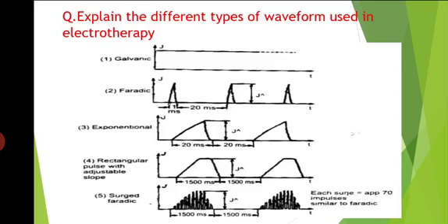Faradic current. Faradic current is a sequence of pulses with a defined shape and current intensity. The pulse duration is about 1 millisecond with a triangular waveform, and an interval duration of about 20 milliseconds. Faradic current acts upon muscle tissues and, upon the motor nerves, produces muscle contraction. There is no ion transfer and no chemical effect. It is used in the treatment of muscle weakness.